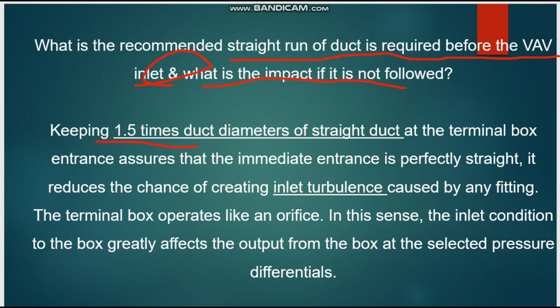Keeping 1.5 times duct diameter of the straight duct at the terminal box entrance ensures that the immediate entrance is perfectly straight. That means suppose you have a VAV here, and this is the supply duct and this is the return duct, and you should not have any immediate elbow like this. This elbow must be avoided. So that is the reason you have to keep 1.5 times D. For example, if the inlet diameter is 200 mm, it means 1.5 into 200. So that distance you must follow.